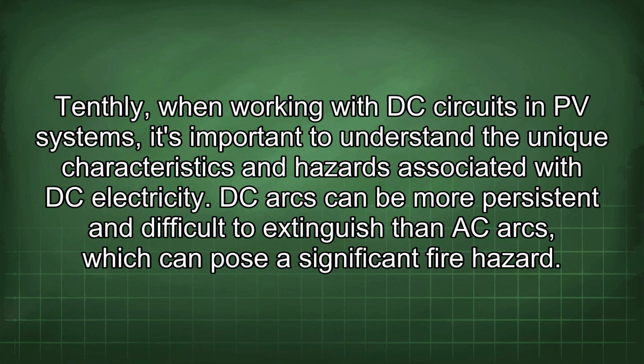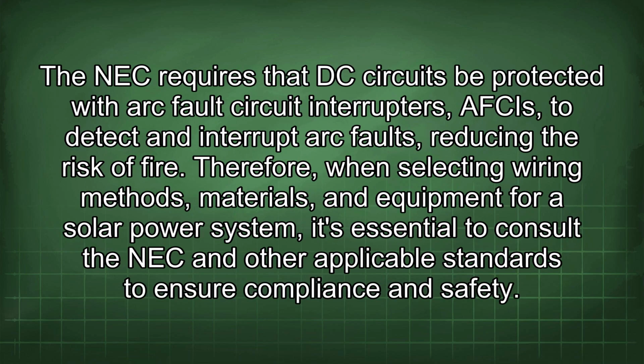Tenthly, when working with DC circuits in PV systems, it's important to understand the unique characteristics and hazards associated with DC electricity. DC arcs can be more persistent and difficult to extinguish than AC arcs, which can pose a significant fire hazard. The NEC requires that DC circuits be protected with arc fault circuit interrupters designed to detect and interrupt arc faults, reducing the risk of fire.